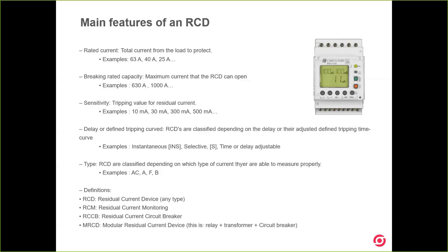Let's follow with RCM — residual current monitoring. This is a type of residual current device used to monitor the leakage on the installation. You have an example in the slide: I've included a picture of the RGU10V, which is a relay, an RCD type B that I will explain further. This relay, the RGU10V, can be used as an RCM because with its display you can follow the leakage in real time.